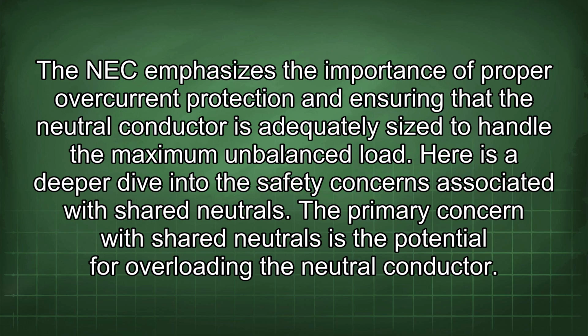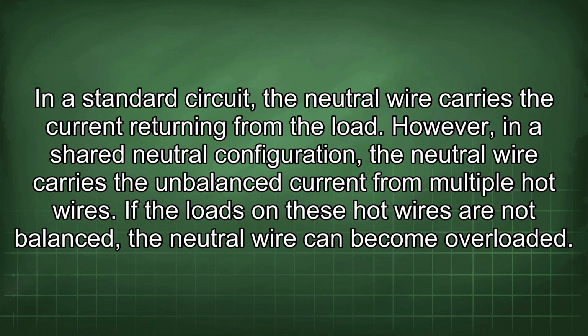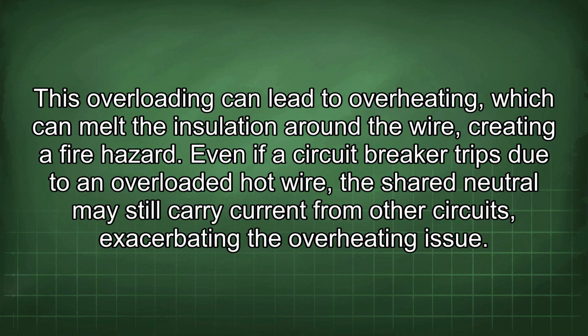The primary concern with shared neutrals is the potential for overloading the neutral conductor. In a standard circuit, the neutral wire carries the current returning from the load. However, in a shared neutral configuration, the neutral wire carries the unbalanced current from multiple hot wires. If the loads on these hot wires are not balanced, the neutral wire can become overloaded. This overloading can lead to overheating, which can melt the insulation around the wire, creating a fire hazard. Even if a circuit breaker trips due to an overloaded hot wire, the shared neutral may still carry current from other circuits, exacerbating the overheating issue.